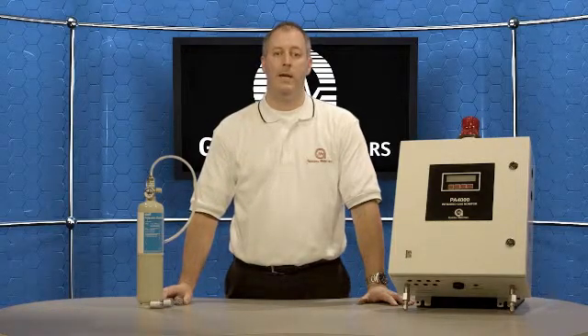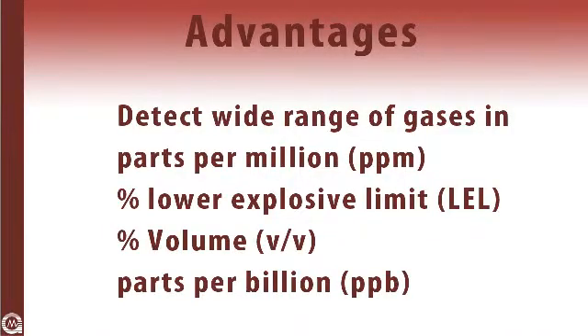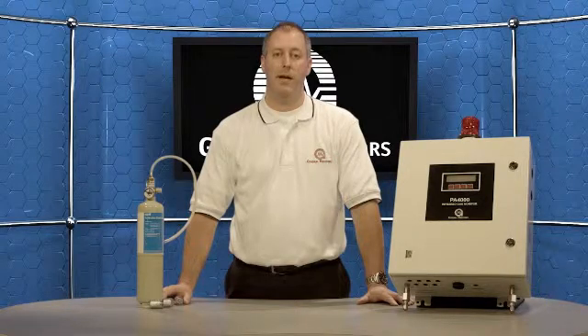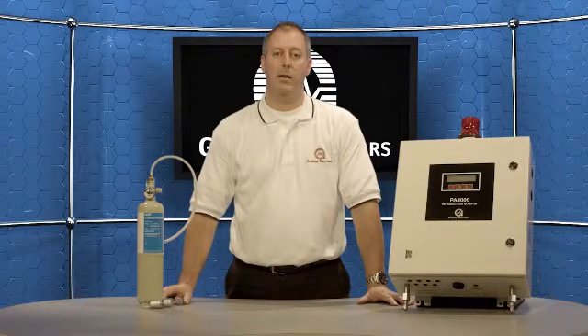The main advantage of the PA4000 is that it can detect a wide range of gases in PPM, percent LEL, percent by volume, and in some cases, PPB ranges. It is highly selectable to the target gas and has the ability to operate long periods of time without adjustment or zero drift.